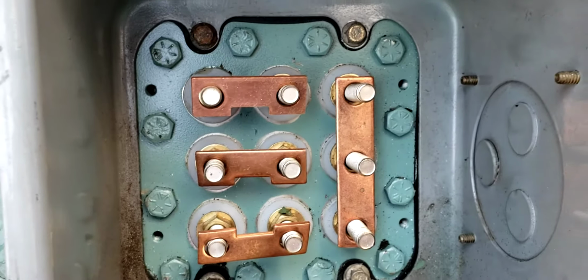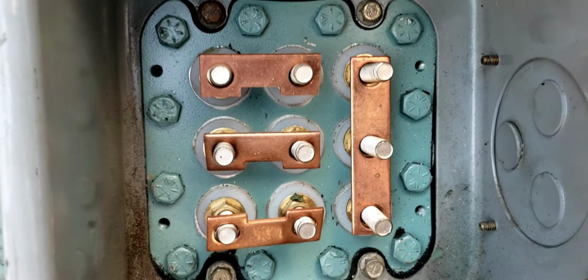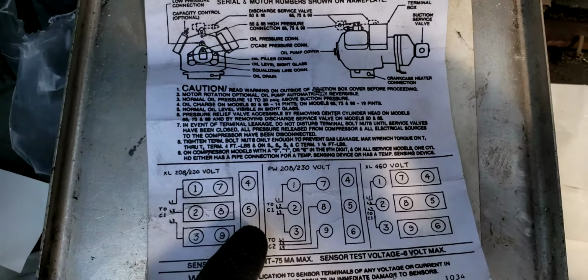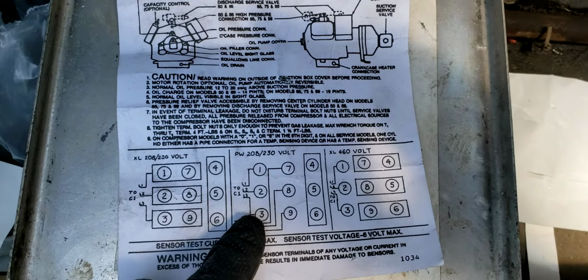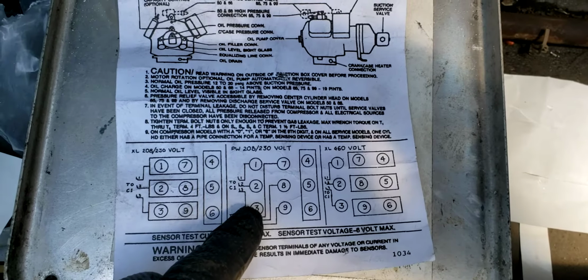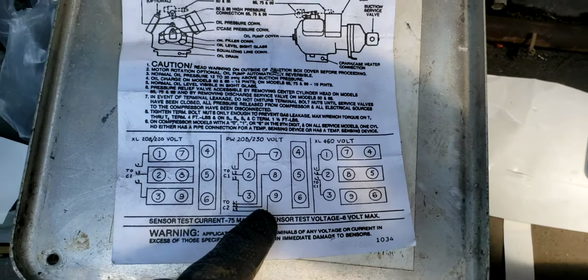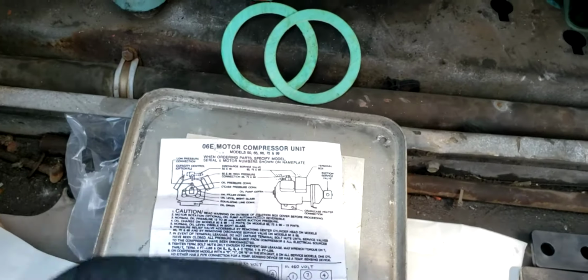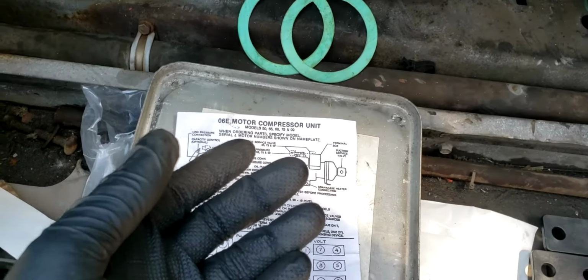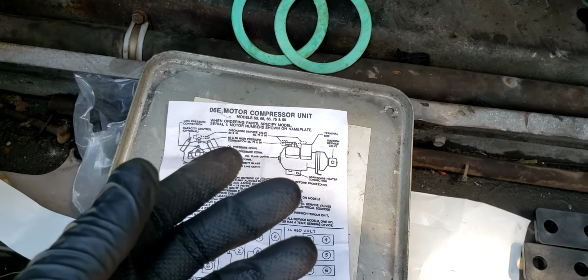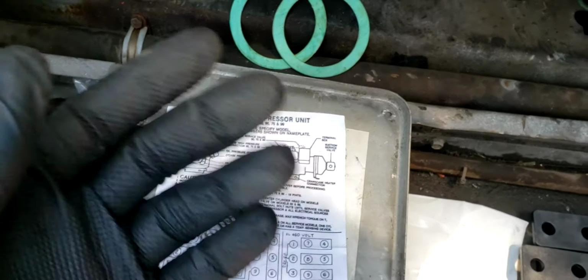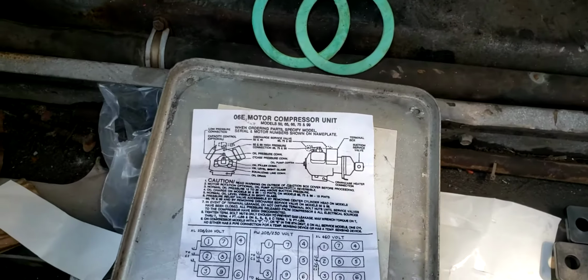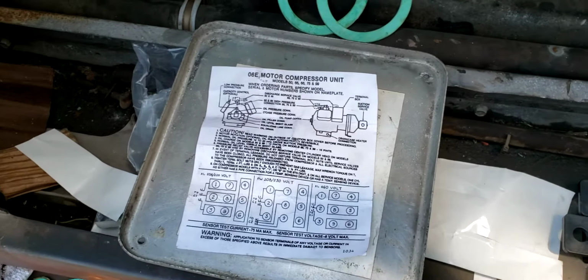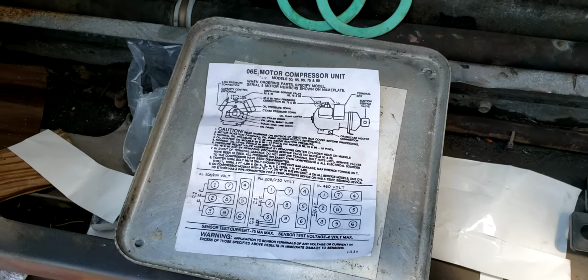Otherwise, you have one going clockwise. Let's say the first winding for C1 is going clockwise, and then you have the voltage line 1, line 2, or any two phases reversed on the C2. Then you have one winding going clockwise, the other one going counterclockwise, so it's going to cancel out, and the compressor is going to just pull a lot of amperage, probably blow your breaker or your fuse, and possibly burn itself out.